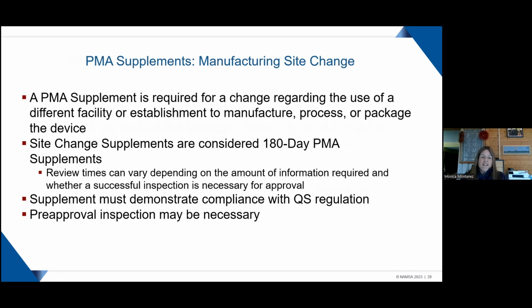So let's talk about manufacturing site changes. A PMA supplement is required for these types of changes, or for a change of establishment to manufacture, process, or package the device. So these site changes are considered 180-day PMA supplements. The review times, of course, can depend on the amount of information that you need to submit in these types of supplements, and whether a successful inspection is necessary for approval. This supplement must demonstrate compliance with the quality system regulation, because with a lot of these manufacturing changes, you have to requalify your move to a new site. So a pre-approval inspection may be necessary depending on how much is moved and how large.